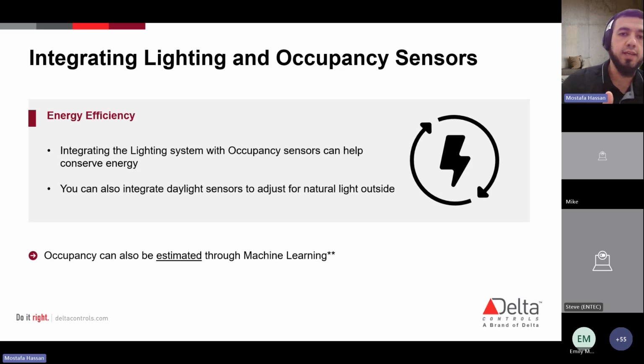We're going to talk a little bit about lighting and occupancy briefly here. So occupancy sensors, as shown on the previous slide, there was an occupancy sensor there, and we use that along with our HVAC system, our VAV system, to adjust settings based on movement, right? Again, I'm not going to go deeply. This is pretty self-explanatory, but when the room is unoccupied, you can dim the lights, you can turn down your HVAC systems. You can reduce air conditioning, maybe modulate the VAV back down to a specific CFM, lowering the energy usage, right?